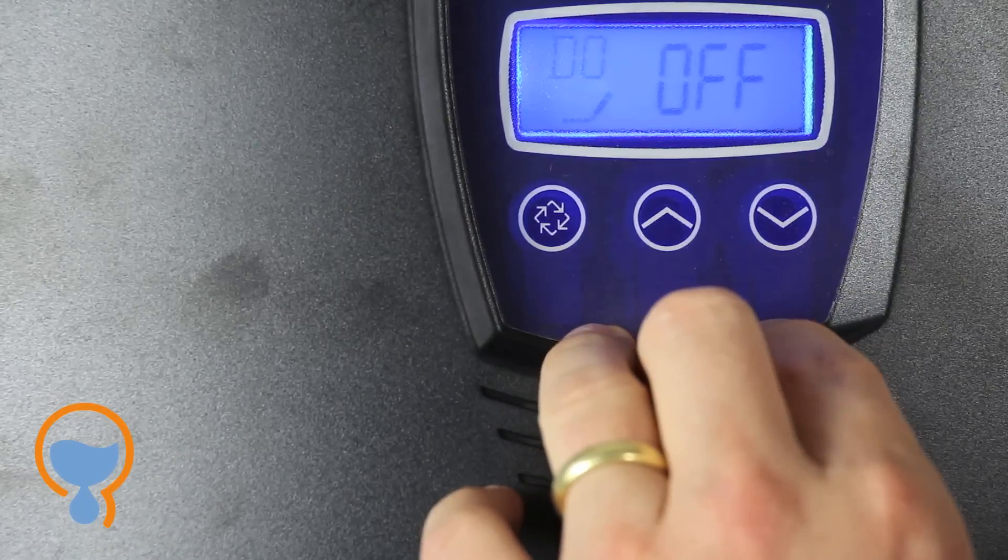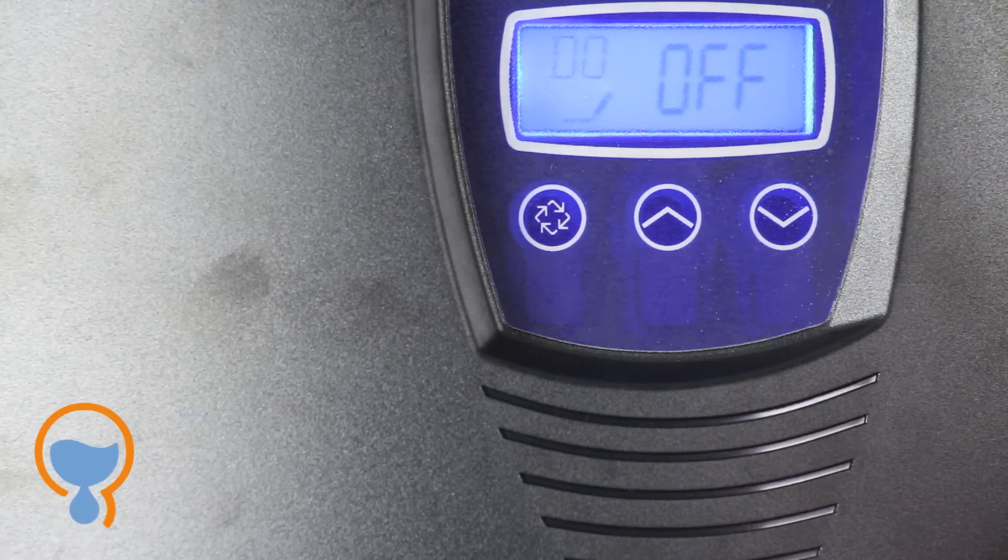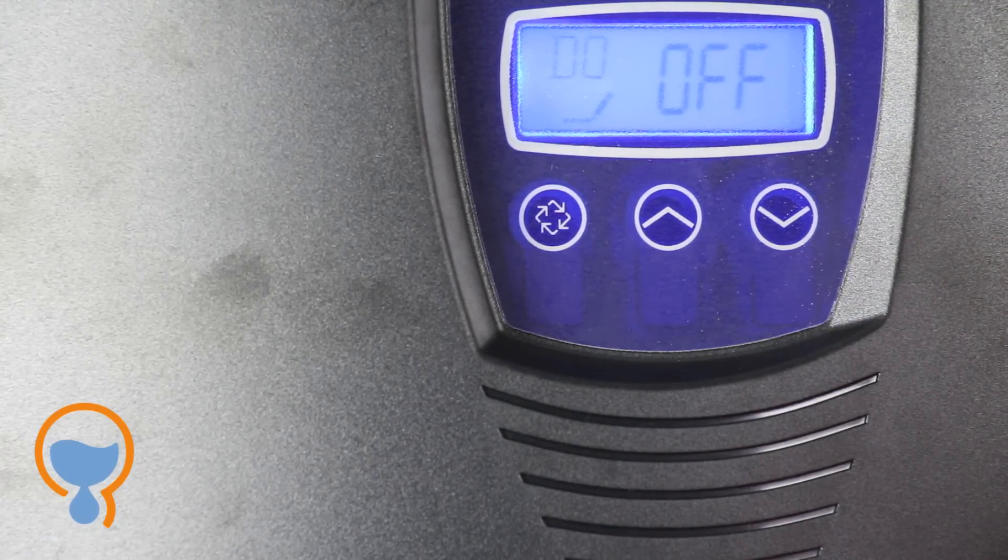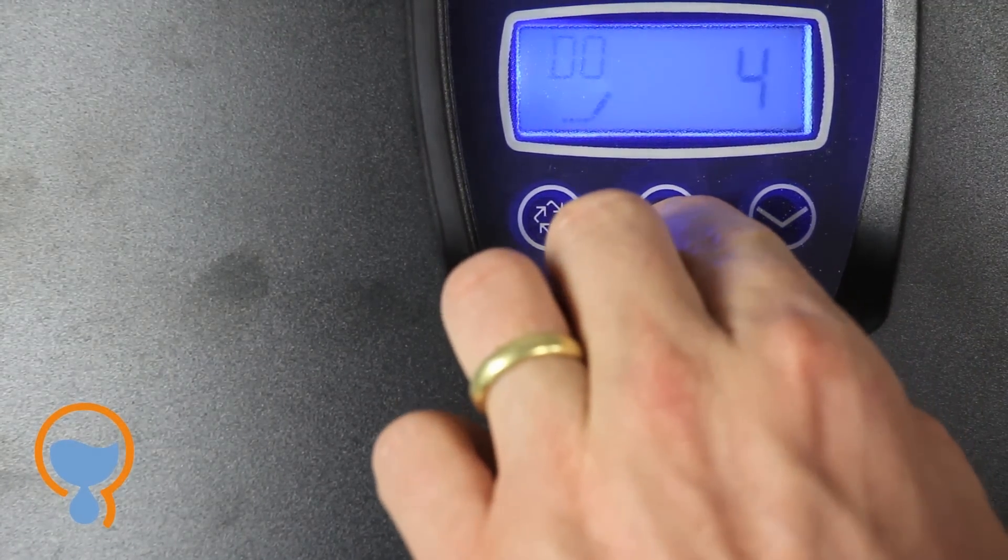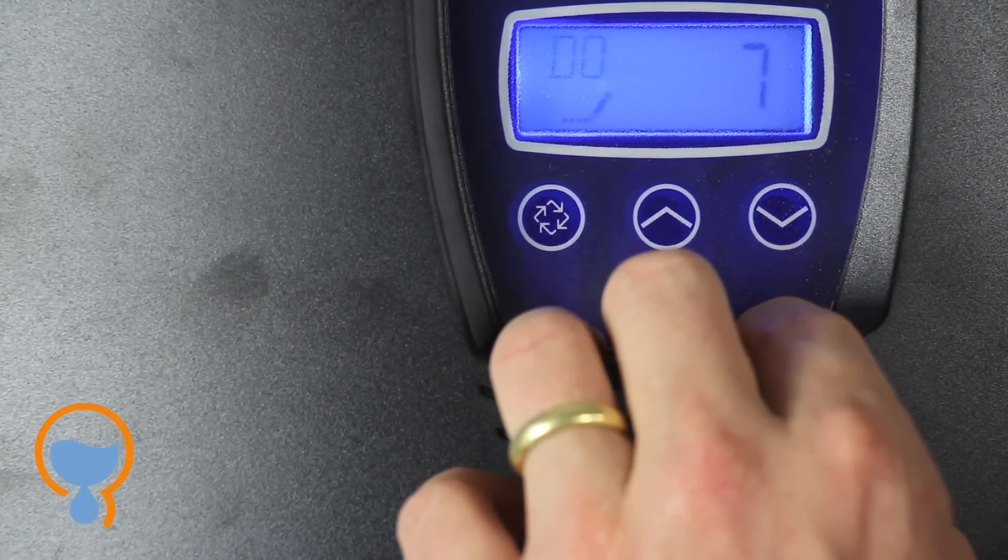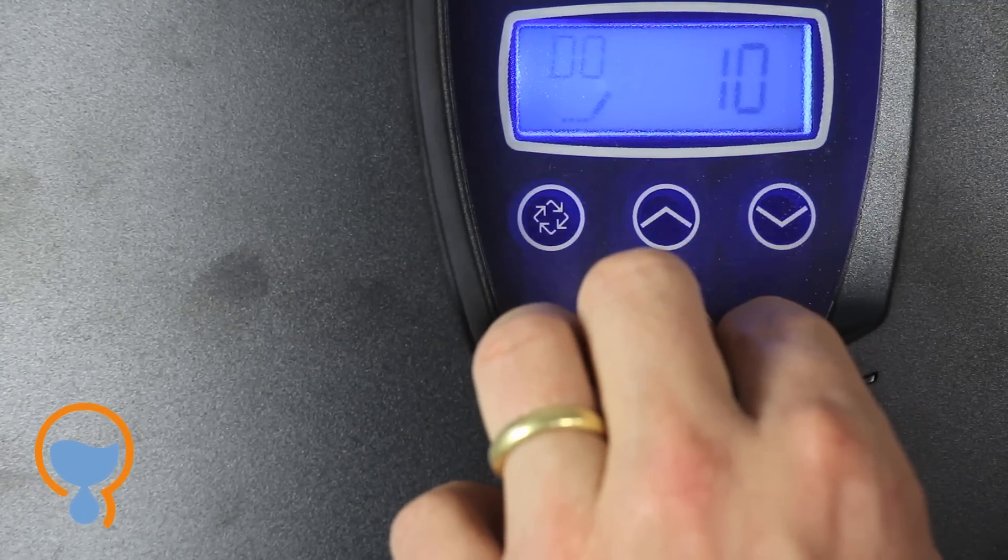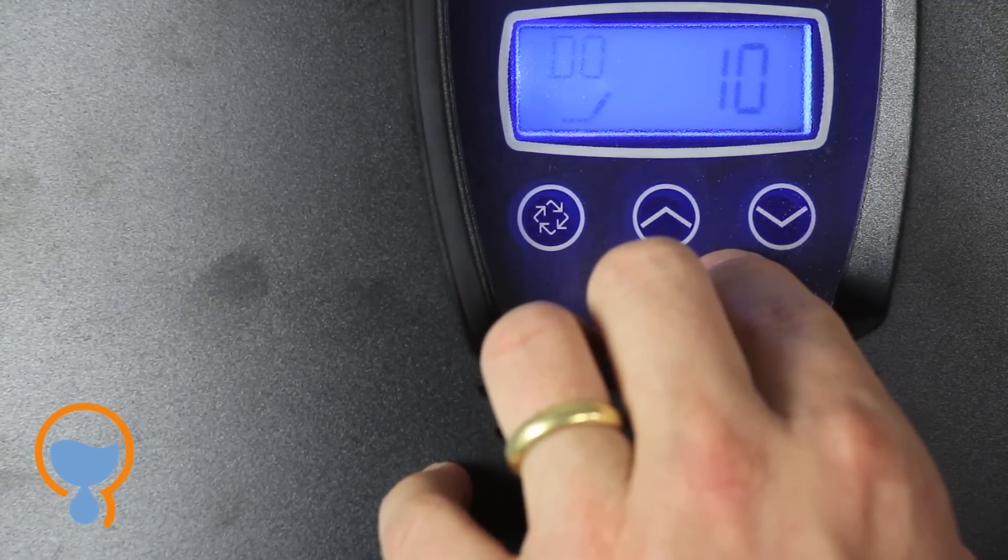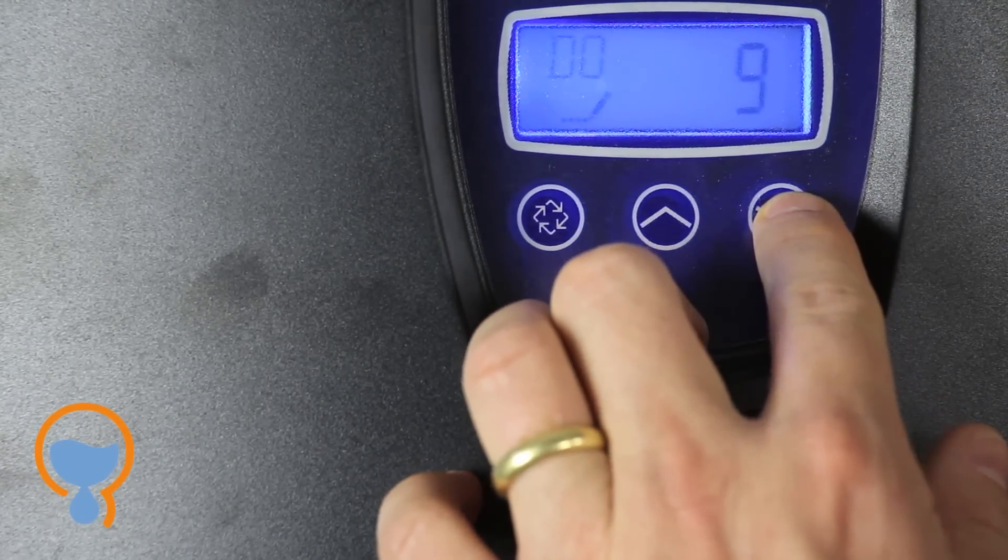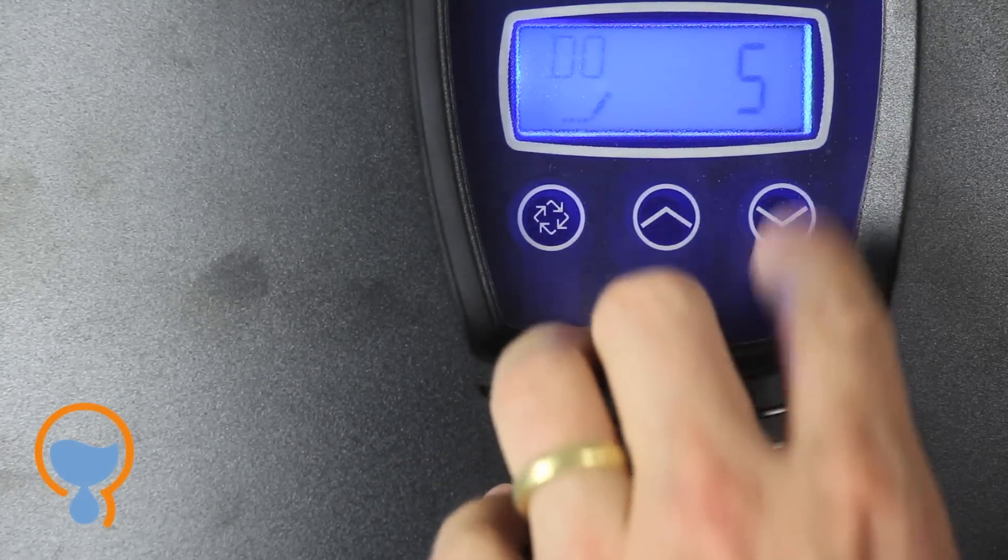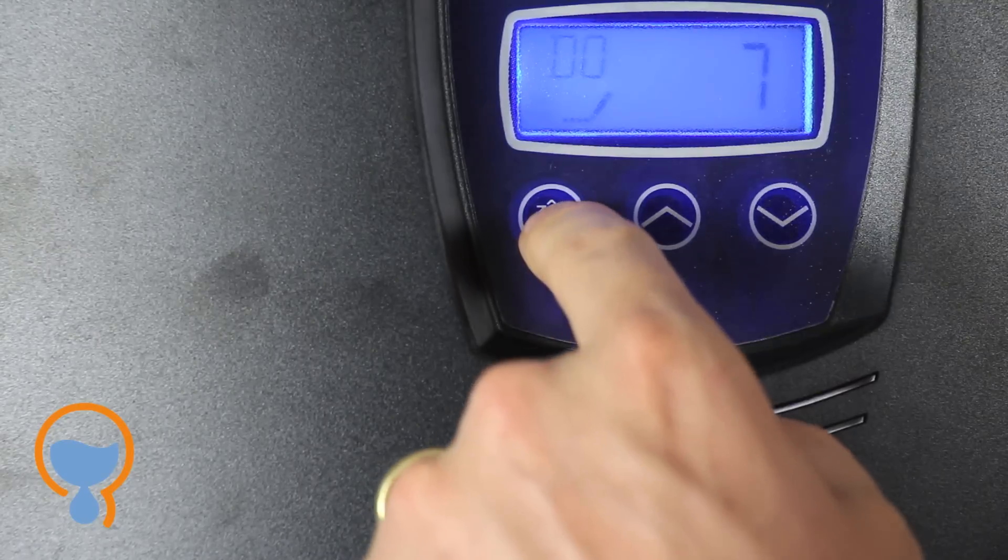Day override. Day override tells the softener to regenerate after a certain number of days has elapsed if it hasn't already regenerated because of the amount of water that's been used. If you're on a well you don't want it to go any more than 7 days between regenerations. So you can use a 7 value. If you're on city water you can use a value of 10. If the water that you've got has exceptionally high iron then you don't want to go more than 5 days. So if we assume very high iron we'd set it to a 5 day override. Otherwise for well water it would be 7. So that's what we'll use here.